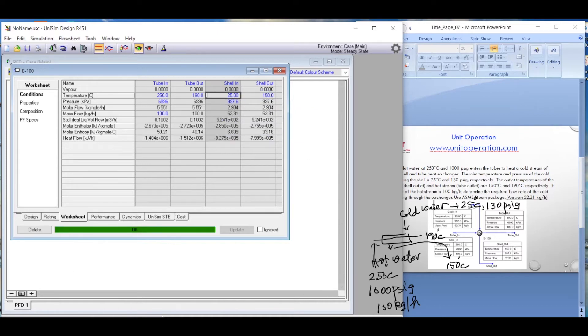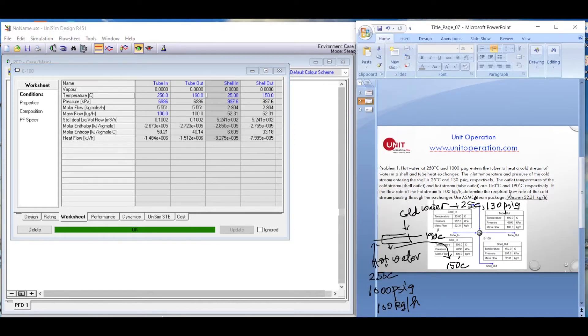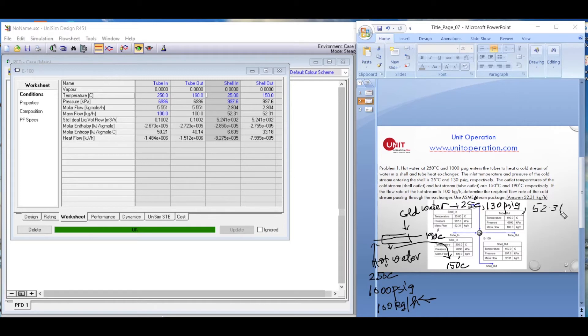The moment we enter the shell side outlet temperature of 150 degrees Celsius, all the degrees of freedom of this heat exchanger are satisfied and it turns green. It automatically calculates all parameters. The required flow rate of the cold water on the shell side comes out to be 52.31 kg per hour — that's how easy it is in the HYSYS environment.